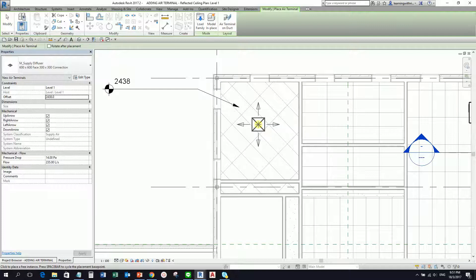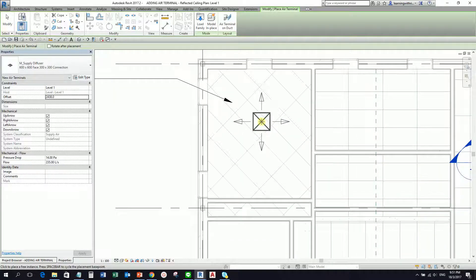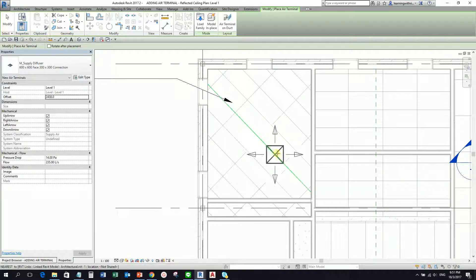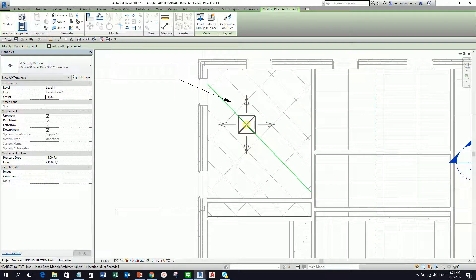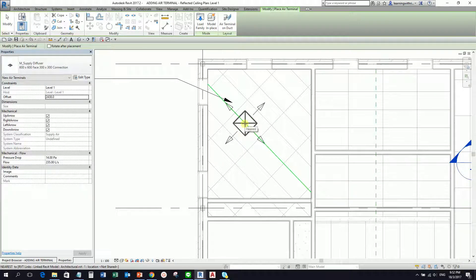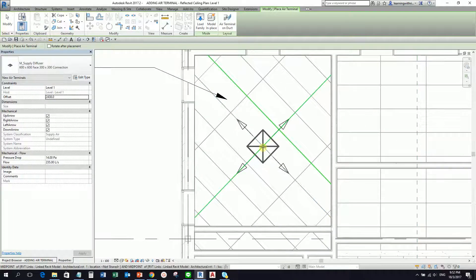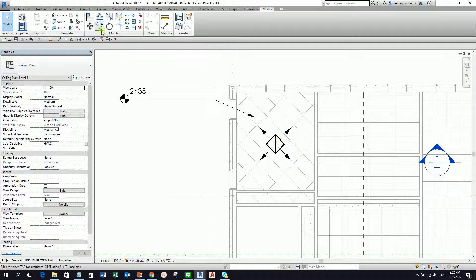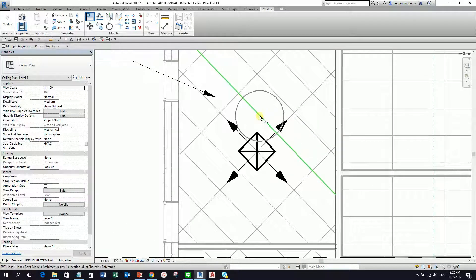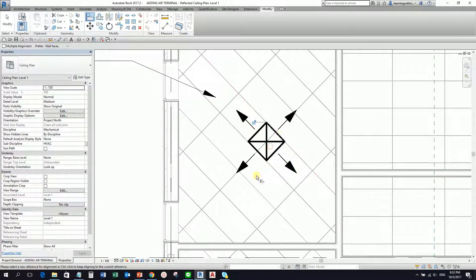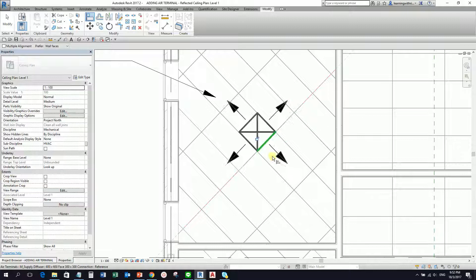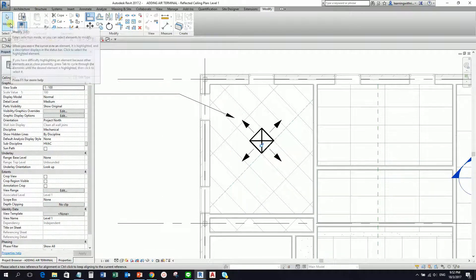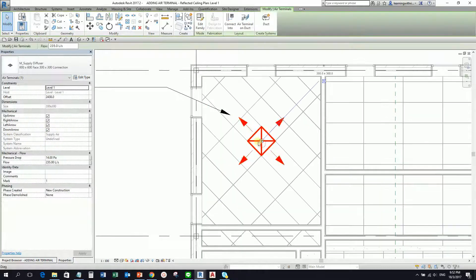If the offset is zero, you will not be able to see the air terminal on your ceiling plan — you can see it on the floor plan but not the ceiling plan. To align the air terminal to the angle of the ceiling grid, hover your pointer over the ceiling grid and press the spacebar to change the orientation. Then place it, select Modify, and use the Align command — select the reference line and then the side you want to align.